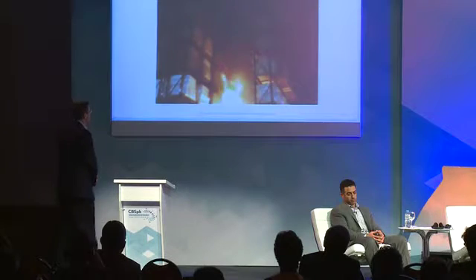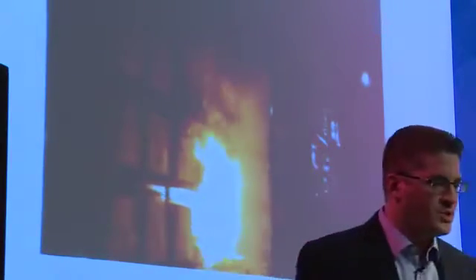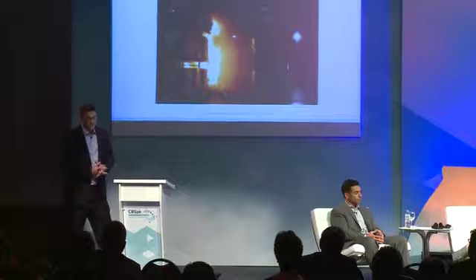Got a little smoke, a little white steam, and a little push downwards there. And next thing you know, we go from a fire that's heading up towards the ceiling very quickly down to a fire that's well controlled in the bottom couple of levels. This seems like still a decent sized fire, but the reality is when you see some of the videos that Gary's going to show you with what this happens with just ceiling sprinklers, this is really incredibly good performance. So we may as well move on to the next video here.